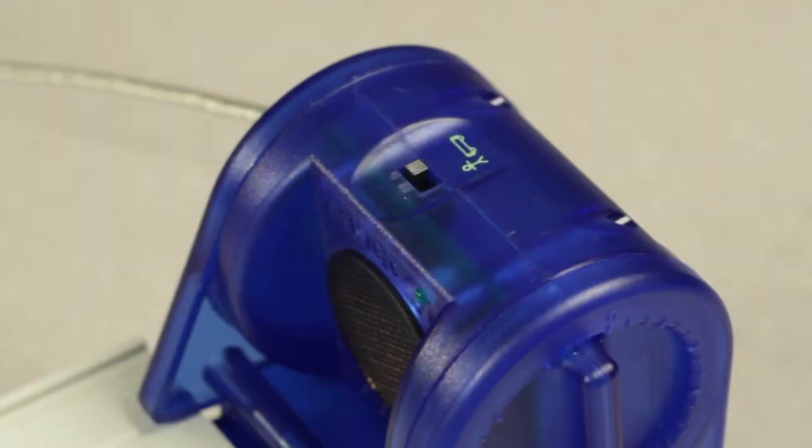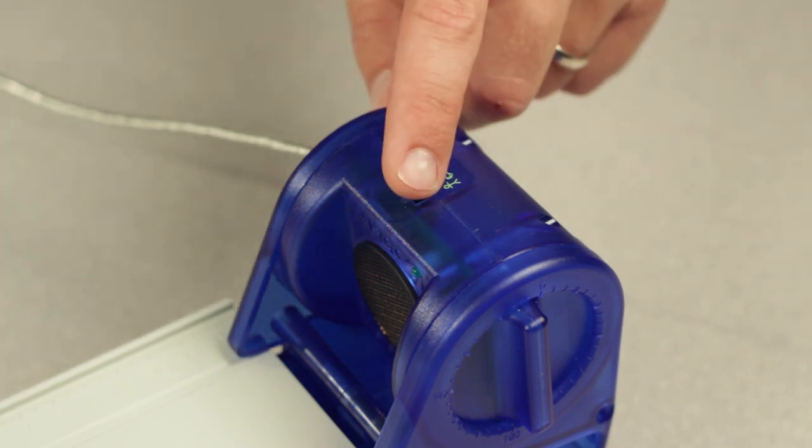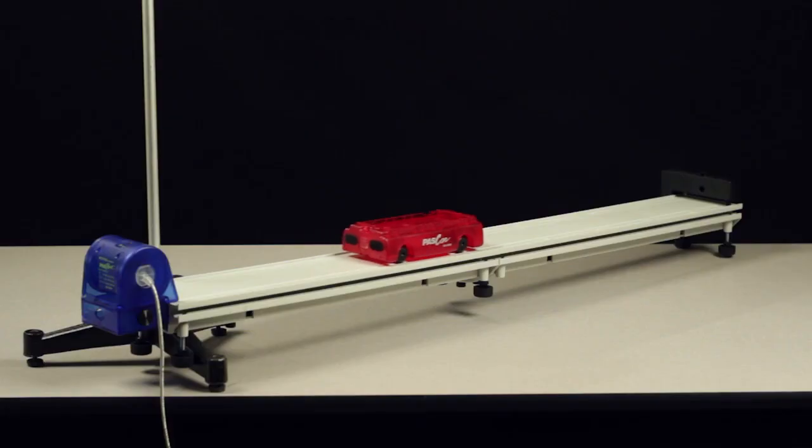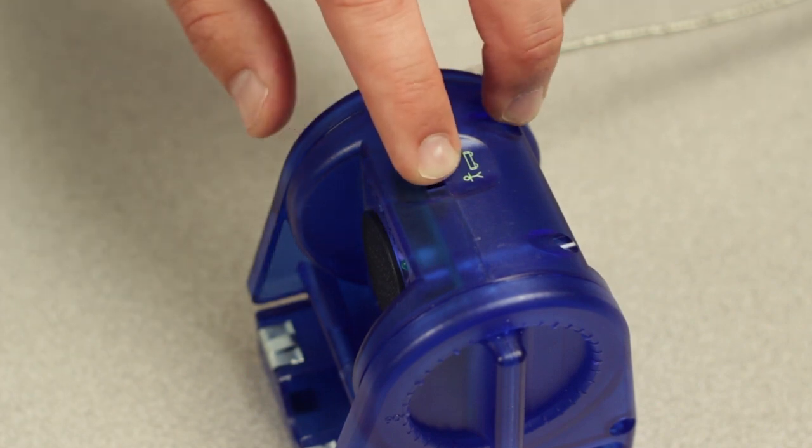On the top of the motion sensor is a selector switch that is used to adjust the range of the sensor when measuring larger objects at longer ranges and smaller objects at shorter ranges. Use the cart setting for smaller, shorter range targets and the person setting for larger, longer range targets.